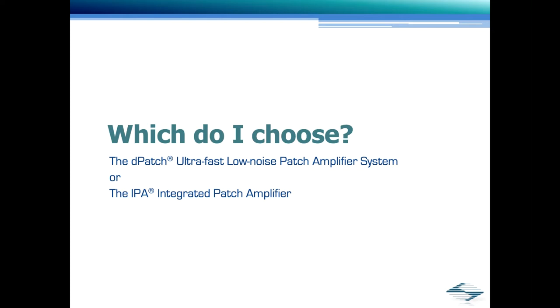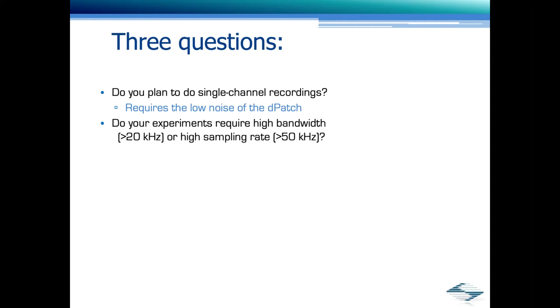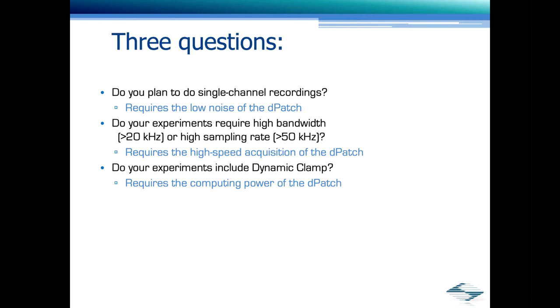Now we have choice of amplifiers. Which one do I choose? Well, typically here, we typically ask three questions. Do you plan to do single channel recordings? Then the low noise option of the DPatch is probably what you need. Do your experiments require bandwidth that is greater than 20 kilohertz and higher sampling rate greater than 50 kilohertz? Then that would also mean the DPatch would be a better choice. Finally, do your experiments include dynamic clamp? Well, the DPatch is the only commercial amplifier out there that has this option. My colleague, Jan, will talk about dynamic clamp option in detail in his talk.